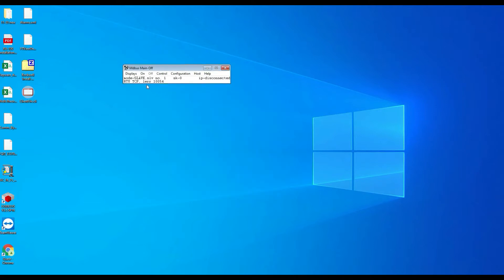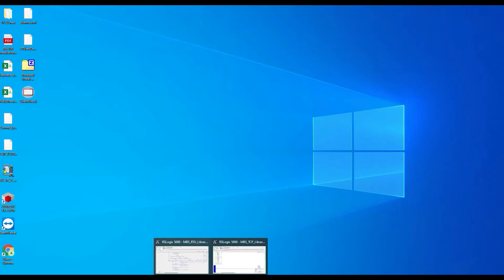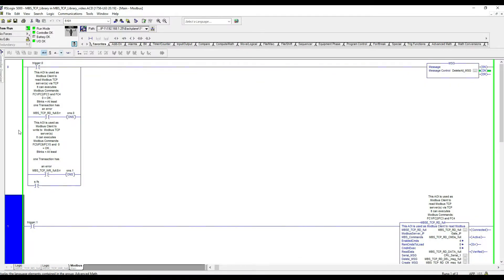I'm using MDBus as my Modbus TCP slave. The protocol is set to RTU TCP using port 502. For the coils and registers I want to interact with, I set this to 80 coils, 80 statuses, 50 input registers, and 50 holding registers. We'll click OK for that basic configuration and turn the slave on so it's ready for communication.